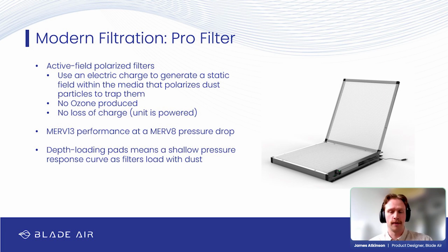We also do what's called depth loading instead of face loading. So in my example of the sieve, I think maybe a coffee filter would have been more apt given our topic of conversation. If you ever use a paper coffee filter, you'll see it flows really quickly at first and then slows down until that last little bit of coffee is just barely dripping out. And that's because the filter has front loaded, right? Those smaller particles get stuck in the front and then block some of the air paths or coffee paths. And as you filter more and more, you have fewer and fewer paths for that to go through. So you get more pressure drop, less flow.